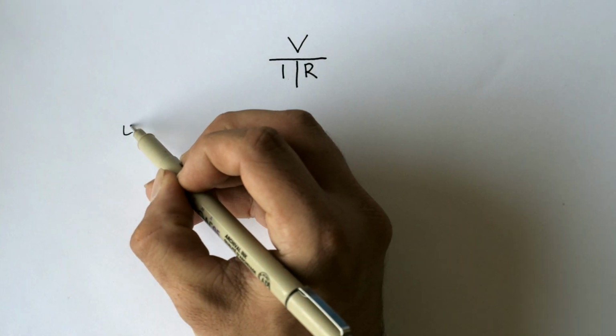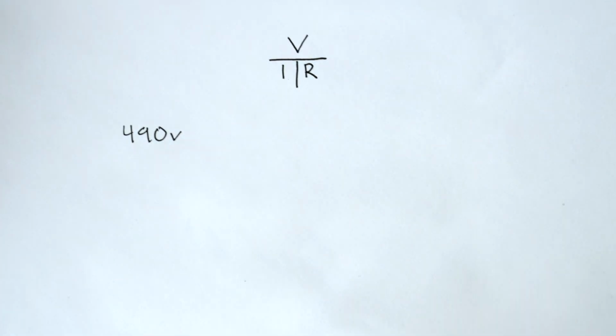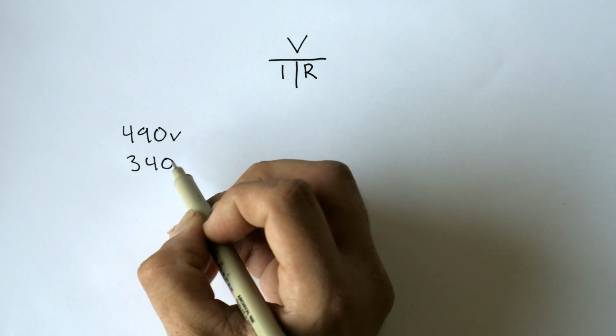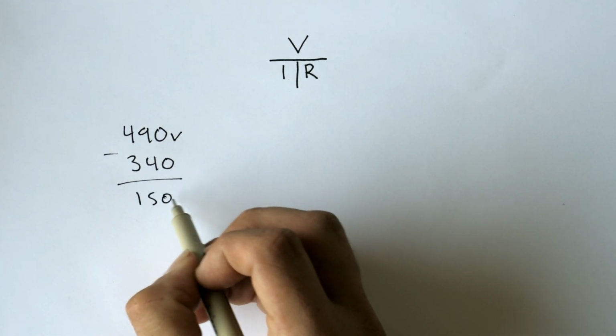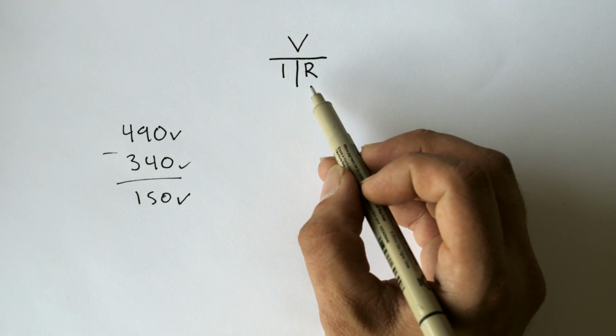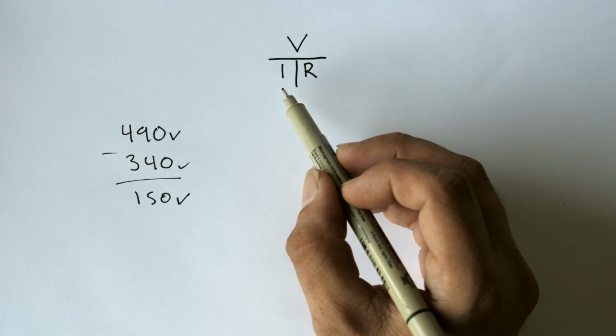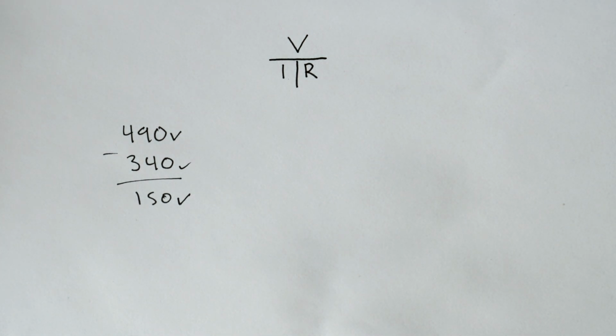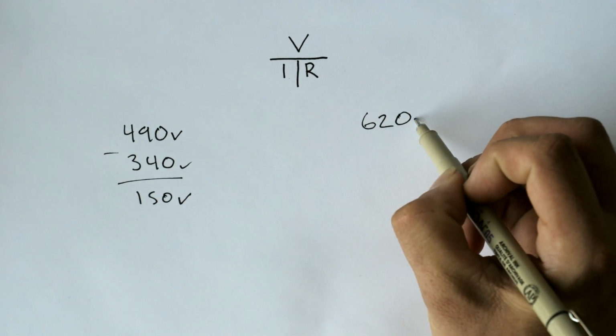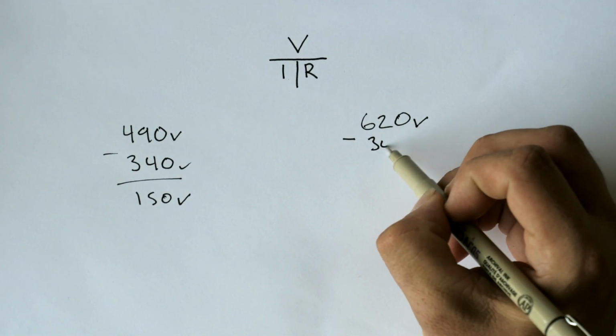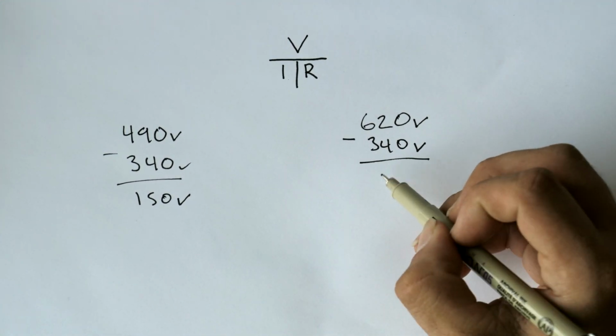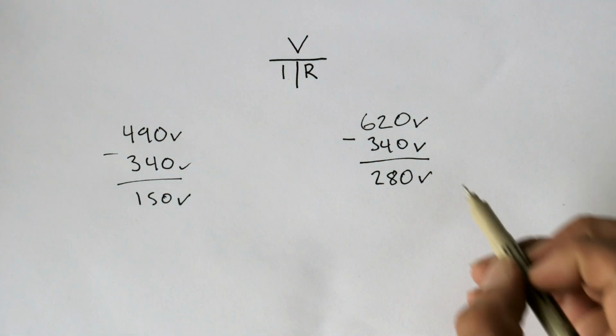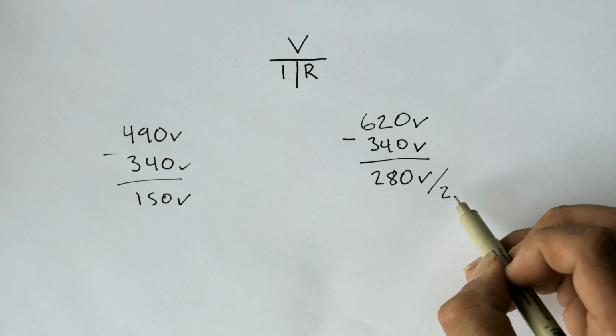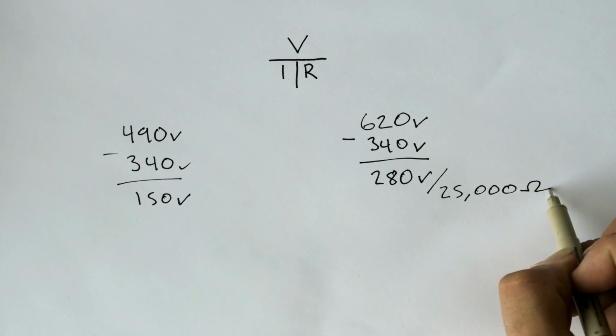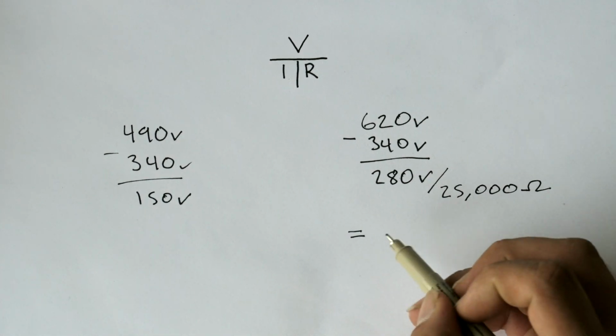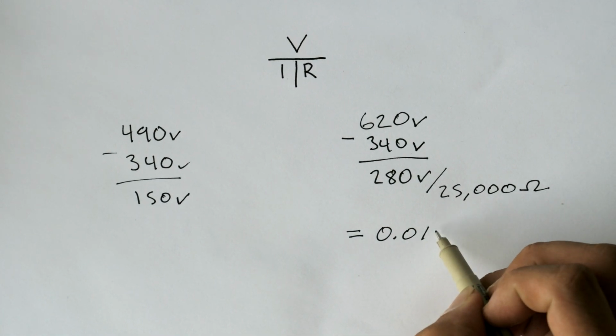Starting with our voltage on the first node of 490, we subtract our desired voltage, giving us a voltage drop of 150 volts. Now to find our resistance value, we know we need to divide voltage by the current passing through. At the first node, we have 620 volts, and we subtract 340, giving us a 280 volt drop. Divide that by the resistance, 25,000 ohms, and we get our current, 0.0112 amps.